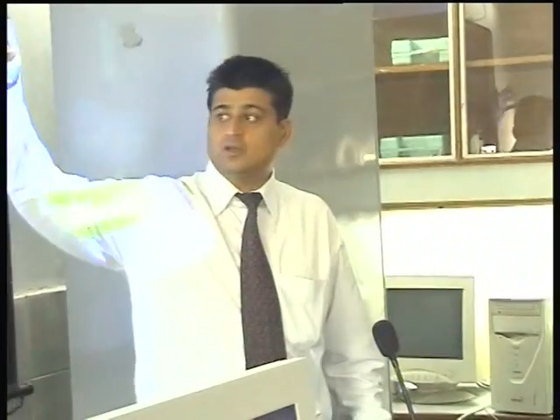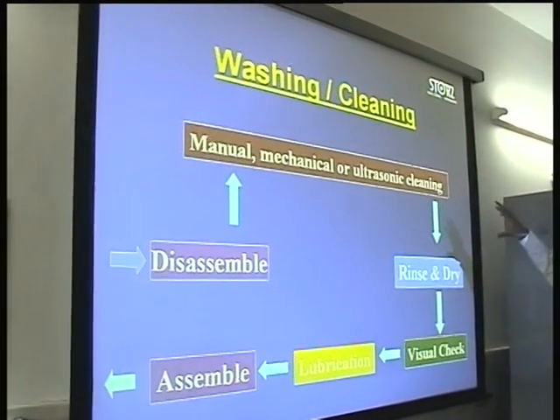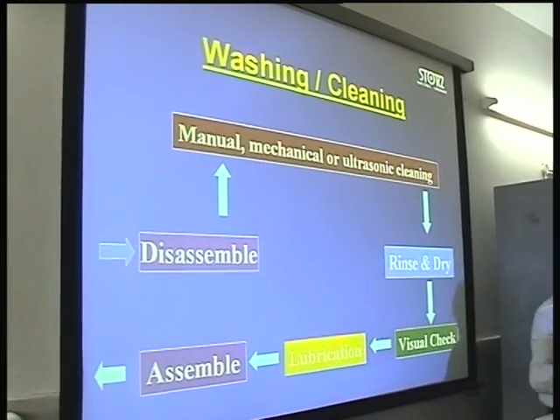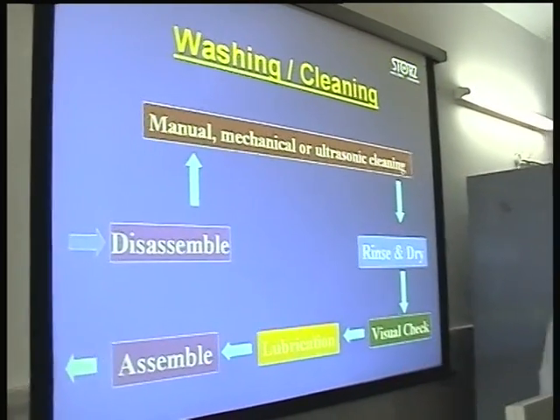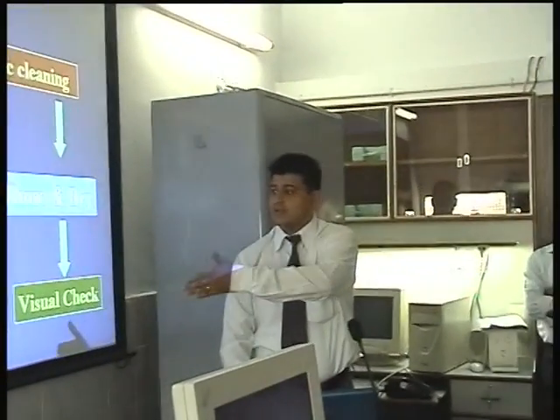We always say sterilization is no substitute for cleaning. So this is the cycle we follow: once we receive the equipment from the theater staff, we dismantle it, do a cleaning, either mechanical or ultrasonic, with fine brushes that go into the lumen, then rinse it, dry it, lubricate, assemble it, and then go for storage.